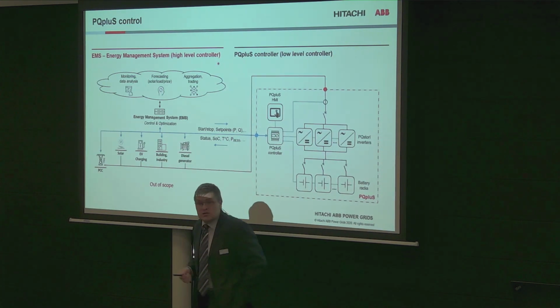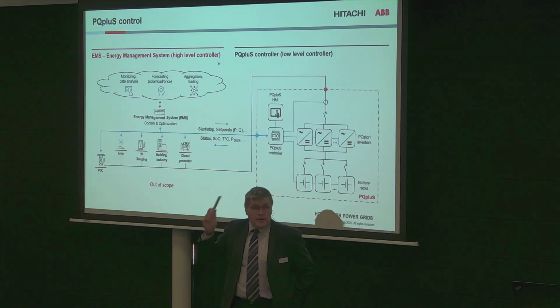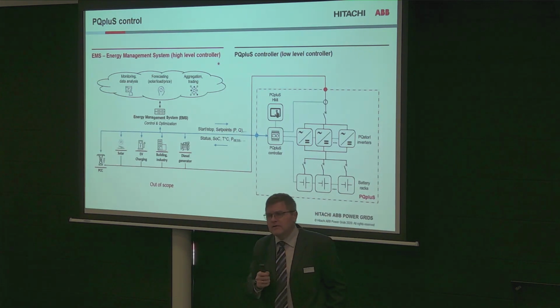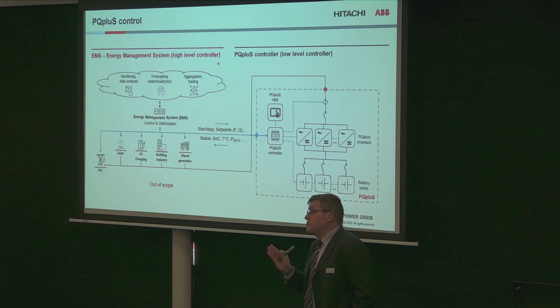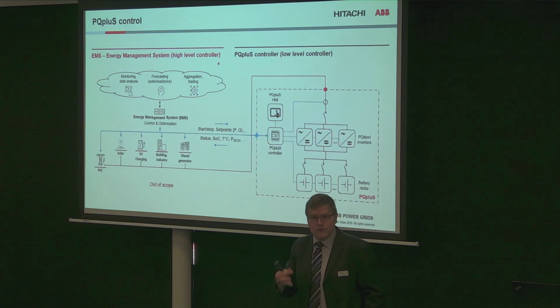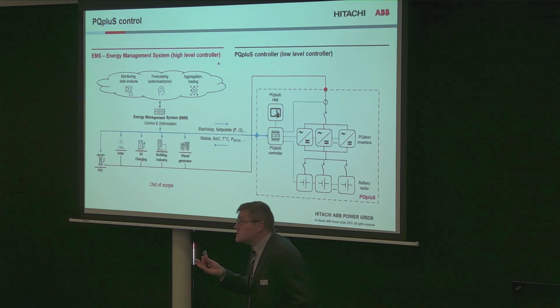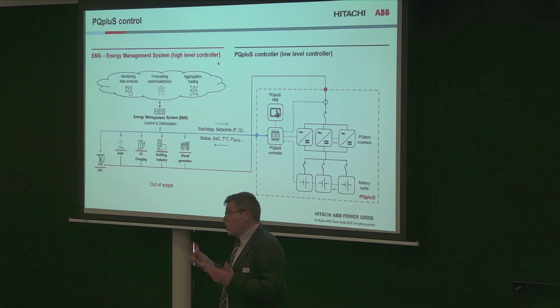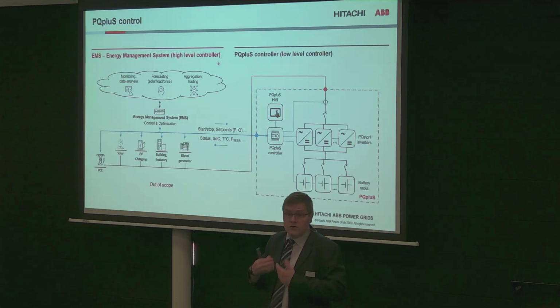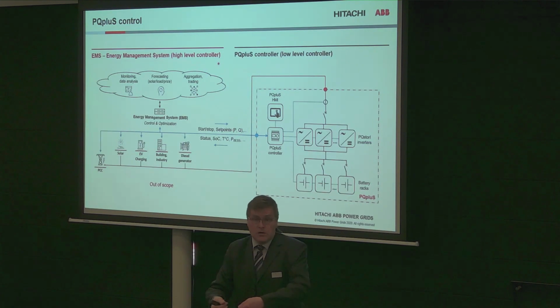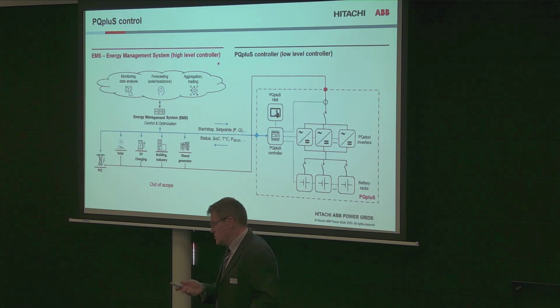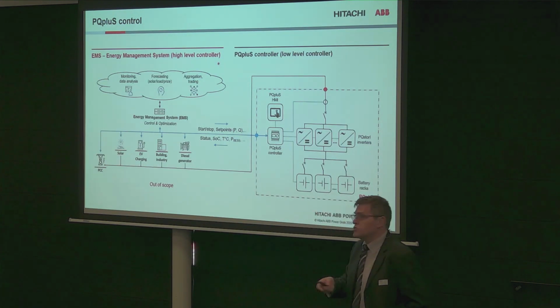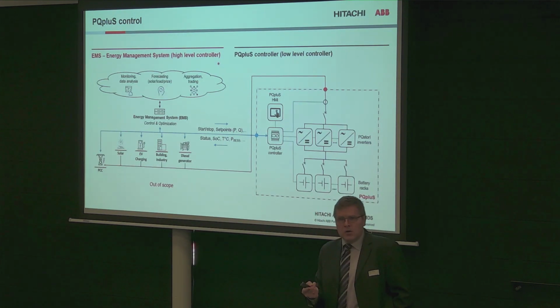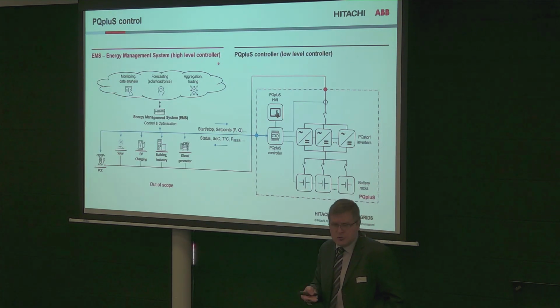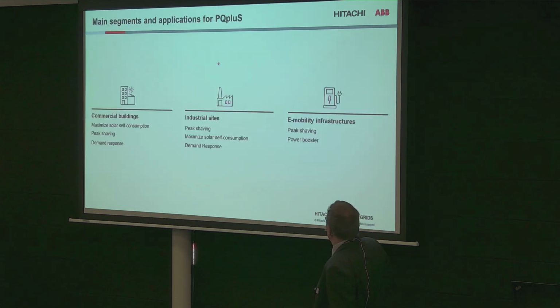Alors, yeah, diesel generator, because now with a battery, I selected an example. We can remove a diesel generator, which is a hot backup for some applications. For example, in hospitals, you need to have what we call hot backup, because if you have a breakdown of the network, but you are in the surgery operation room, you need to continue to operate. So there are critical loads, but also in banks, in data centers. When you have a bank, you cannot stop the computers like that. No, it's not suitable. Okay.